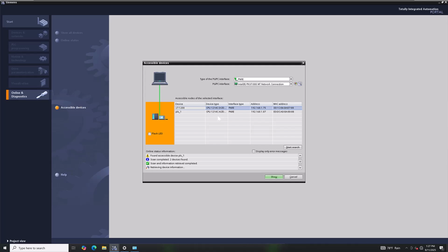So temporarily what I did is I put an N-Tron switch in, which is one I had laying around, which is not managed, so that I can get all three connections. I plug those in there, and I plug my computer in there, and that's why I can see both of these. So for some reason it did not like the setup that was in my managed switch, which was a Stratix 5400. But I just wanted to voice that, because if you do have that combination happening, go ahead and plug directly from your PC into your actual processor, and see if you can see it then.